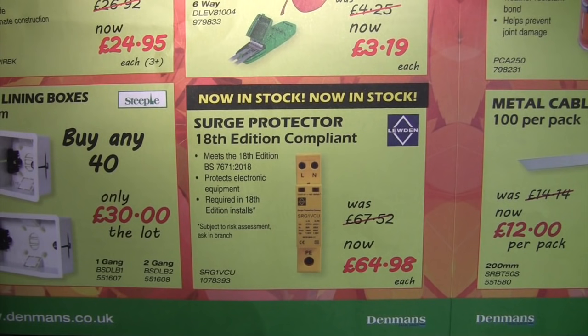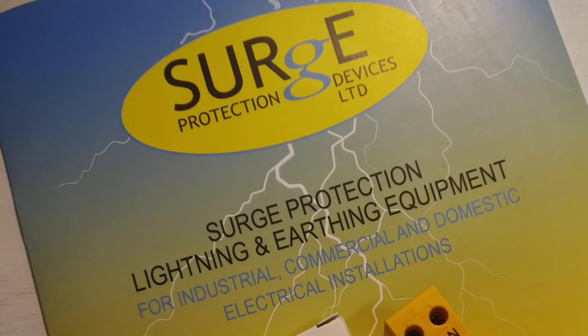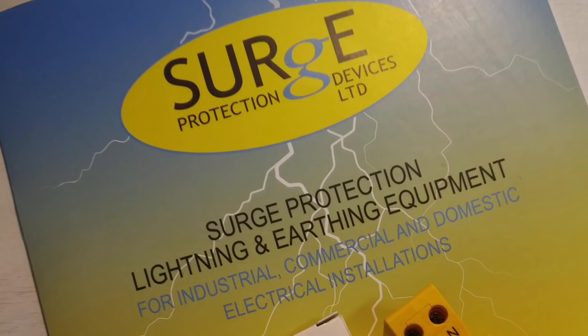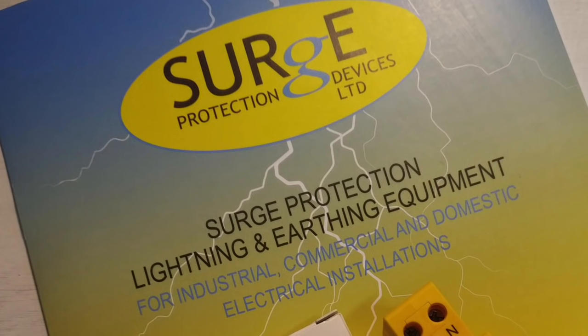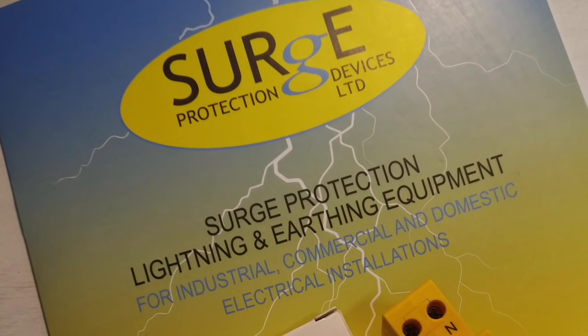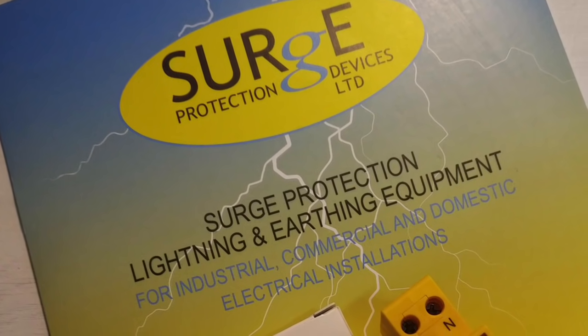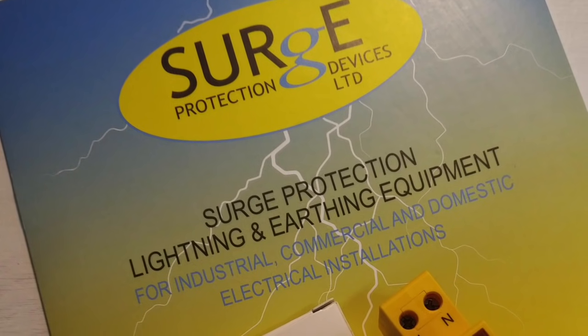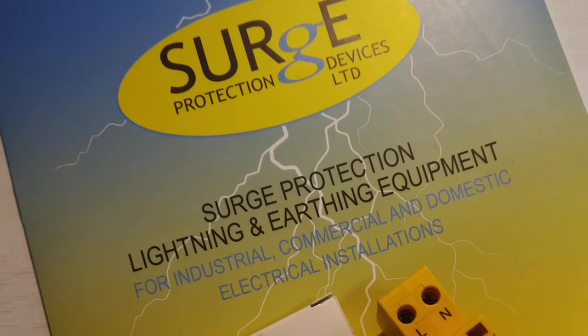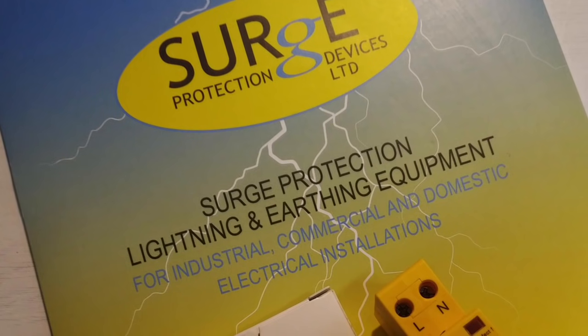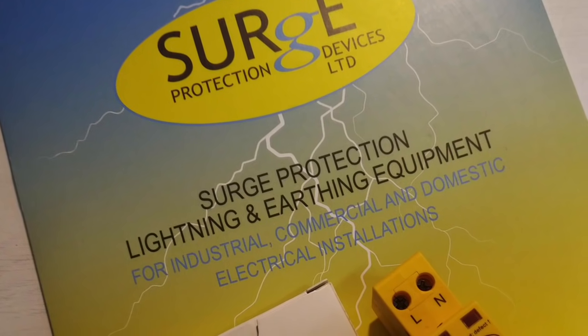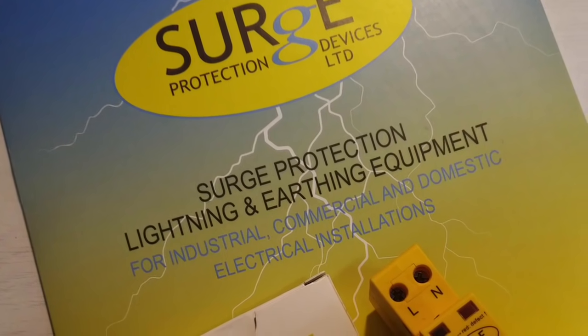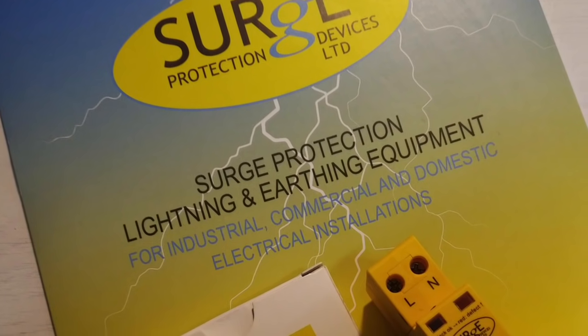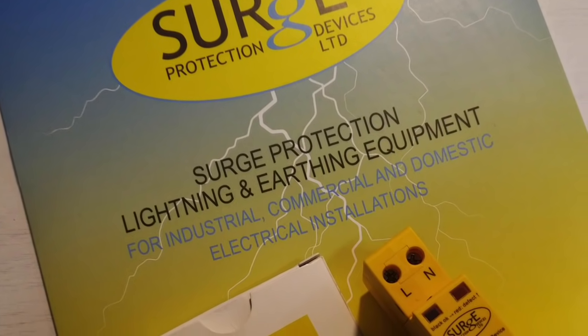So here's the bottom line. If you're on a new commercial installation, chances are you'll be required to fit an SPD, especially if it's in a non-urban location. That is, unless you know the numbers for that daft risk formula and the calculation gets you out of it. If working domestically on a rewire, a new build single dwelling, or on a CU change, then offer it to your client, but it'll cost them about an extra £100 just for the parts by the time VAT and any shipping is added on.